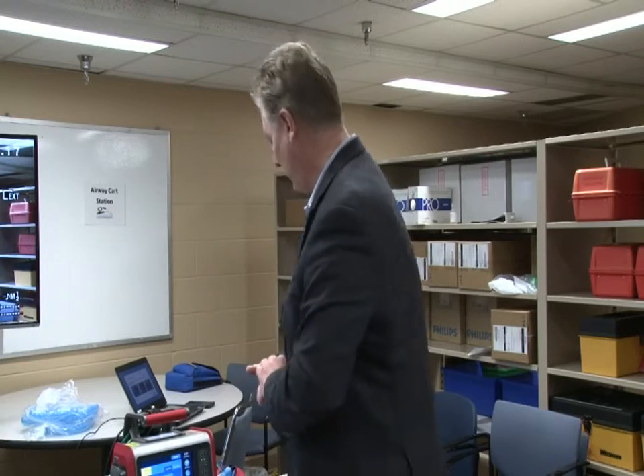Now, if you have end-tidal CO2 or somebody's standing at the ready to do a blood gas, then put them on, wait 2 minutes, get a blood gas, and then adjust from there. But making 10 to 20% moves on that percent minute volume, you're not going to kill anybody. Be extremely careful, and unless you have a very good reason, do not turn it down below 100%. Why would you even have a setting that would go below 100%? We're going to talk about that in a minute. That would be for weaning patients or for known COPD patients.